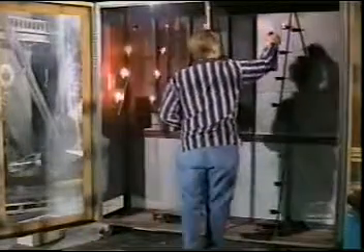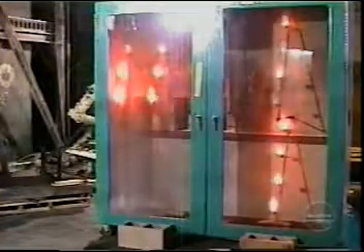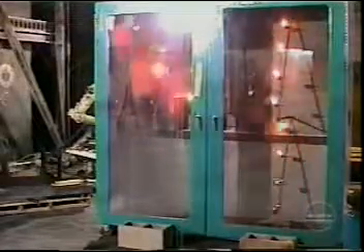First, passing the seat fire toxicity test at the FAA test facility in Atlantic City, New Jersey. Second, passing the 5B heptane pan fire at UL. And third, passing the hidden fire test. This special test shown here, designed by the FAA and British CAA, tests the ability of the agent to flood an area indirectly, such as areas found below deck of the passenger compartment in an aircraft.